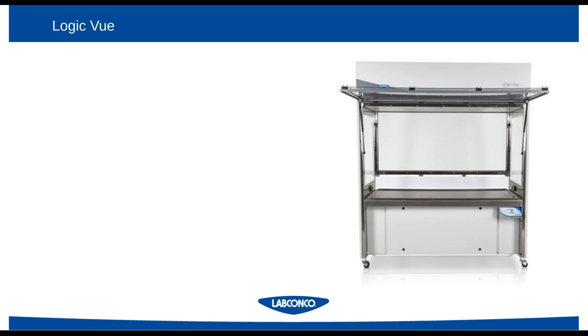It is a console-style single unit that rolls off of a base stand that is built into the system. It's a Class II enclosure, so that means that it's providing both user and product protection, and also provides glass windows on all sides. So in its design, you're able to see any automated instrument performing no matter where you are in the laboratory. And that's really an important step, not only for just being able to see all of the parts of your instrumentation, but also to see it from a distance across the lab.